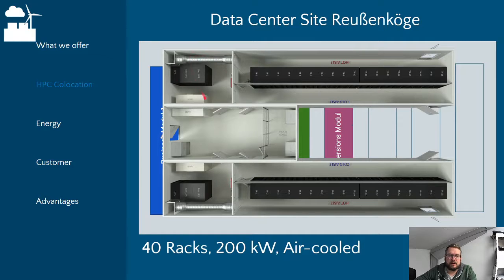The cooling of the technical facilities is handled by the big coolers on top of the data center, shown in another picture, with the necessary cooling air pushed in via ventilation. Here's a bit of a pre-room, since it's windy and rainy here, so it's nicer not to directly access the data center from the outside world. This module will have 40 racks, with an overall IT capacity configured for 200 kilowatts.